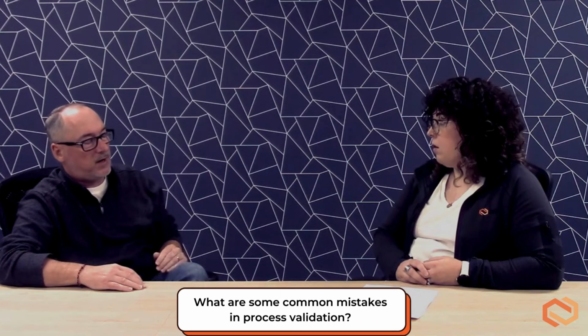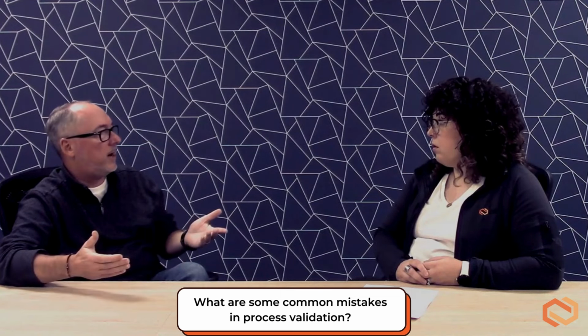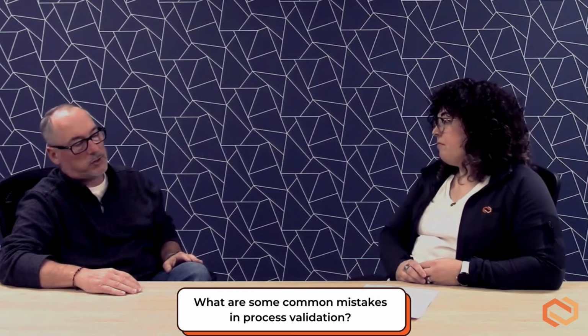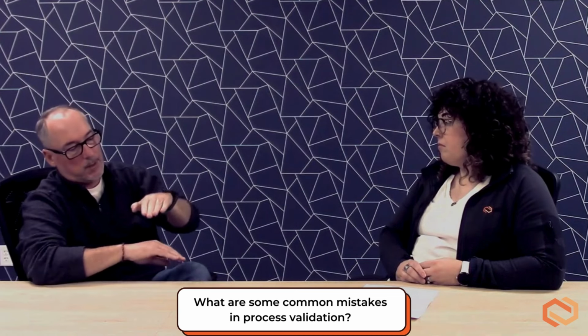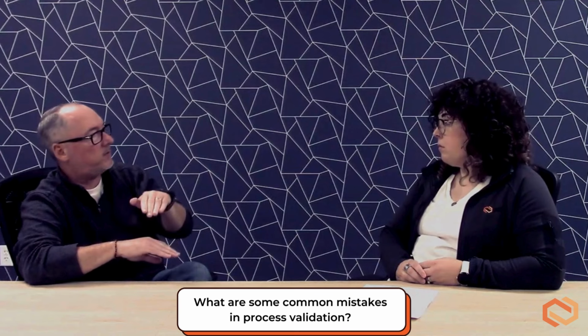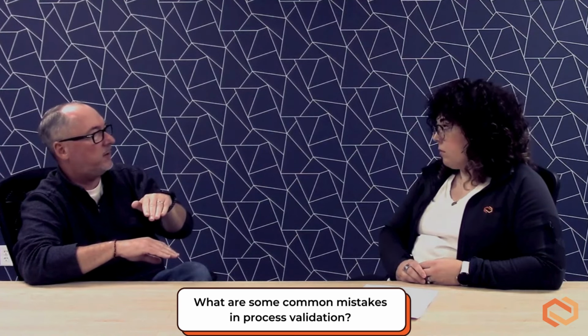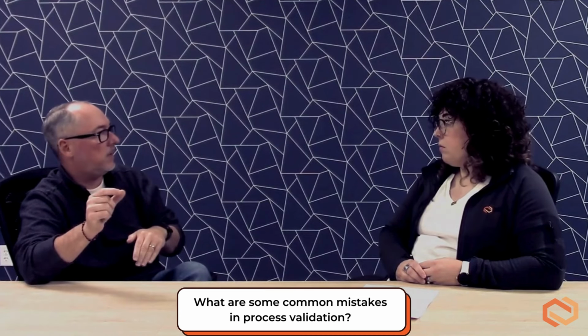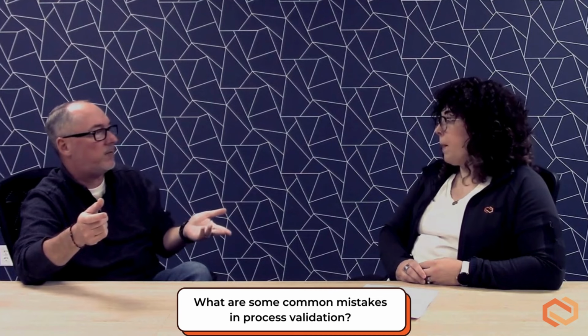Sure. The other thing I see is the seal width, right? Especially for trays. If the platen comes down and is pushing on it too hard, then comes back off, the Tyvek releases a little bit from the tray itself, and we have problems, right? Because now your seal width is thinner. Maybe it's a 3/8 seal, whatever it is.